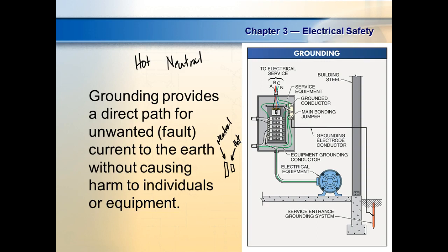I came in, unplugged it, and said it's dangerous, we need it grounded. But I just pulled it out of the wall and turned it around and plugged it back in. He said, well, that won't make any difference, it's AC. I said, yeah, but one of them is hot. So he turned it around. There was no ground on the chassis of the refrigerator, so the breaker didn't trip, because he'd cut the ground plug off and lost that safety.